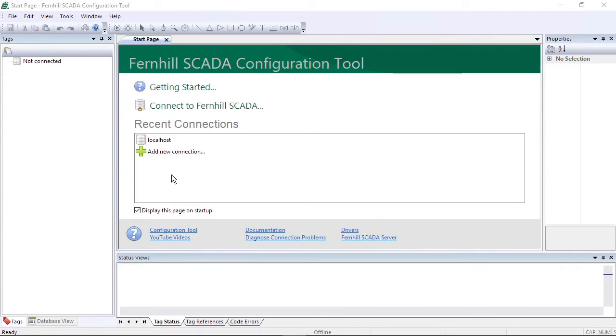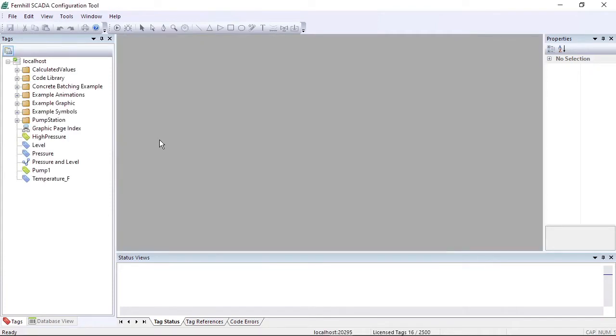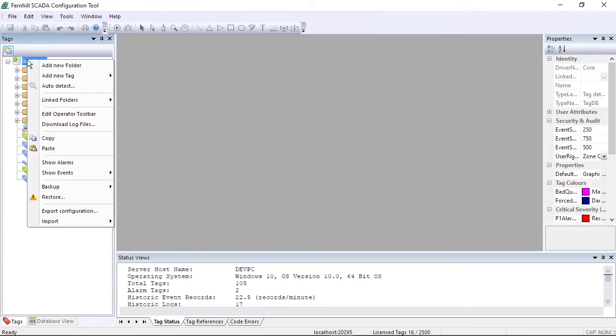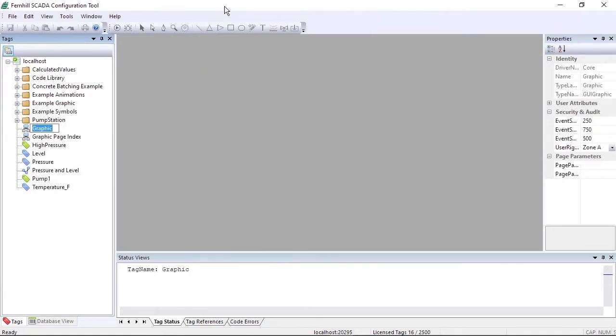We start by connecting the configuration tool to a Fernhill SCADA server. We click the local host entry to connect to the SCADA server running on the local computer. Then we create a new graphic page to work with by right-clicking the root folder, selecting add new tag, followed by core, followed by graphic. Press return to accept the default name of graphic.